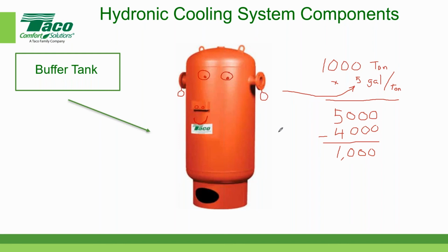What is the difference between a buffer and an expansion tank? Excellent question. A buffer tank stores water almost like storing power in a battery. It creates a place for water to collect when it's entering and leaving the buffer tank. But in an expansion tank, the water does not flow in and out, although we do have some designs where the water does flow in and out, but that's another discussion for another day.